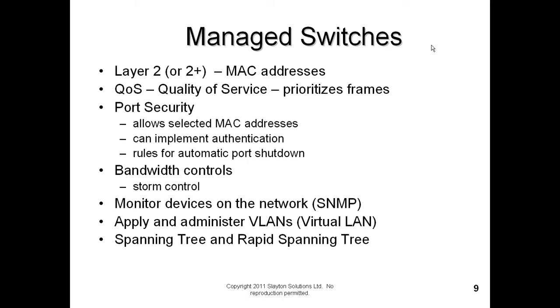One important thing to know is that Ethernet, whether for an IP camera, video encoder, access control panel, or whatever, is not a supervised communication protocol like we understand in the physical security business. In the alarm business we have end-of-line resistors and polled devices, and we want to know that smoke detector is connected even when it's not in alarm. But with Ethernet devices, if somebody turns off a computer, the network doesn't care and no notification is sent out.